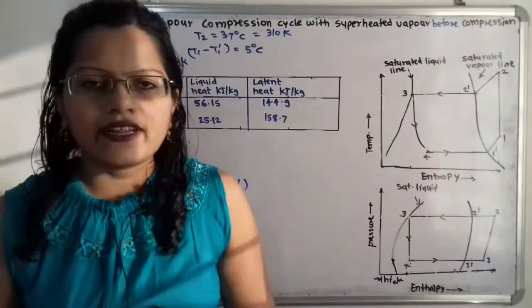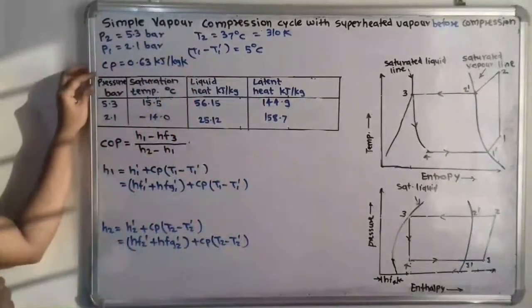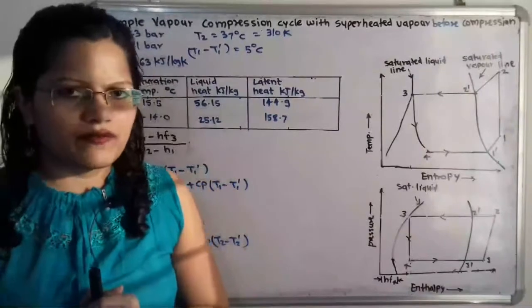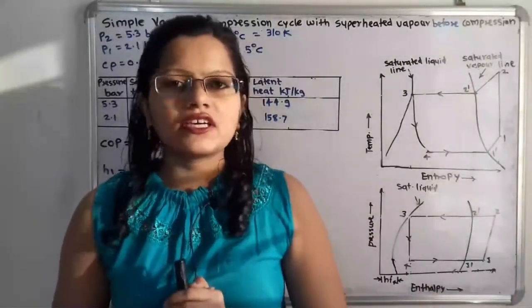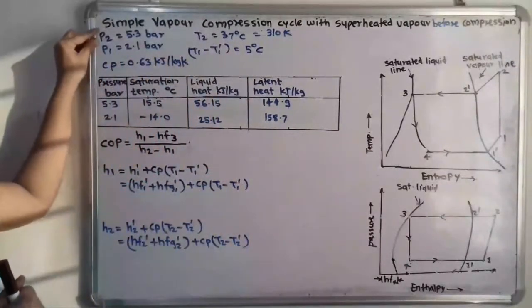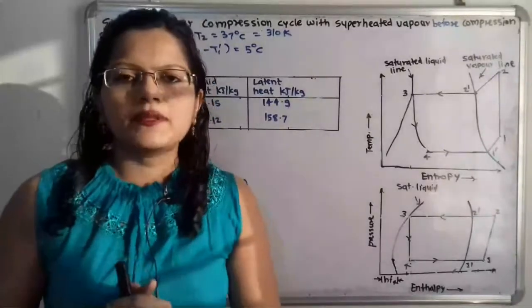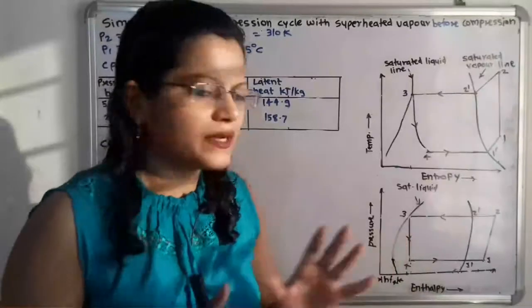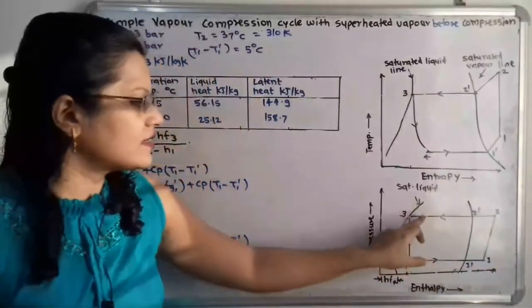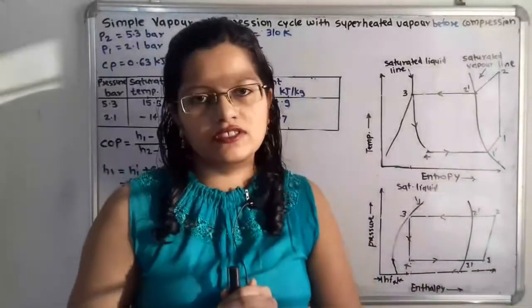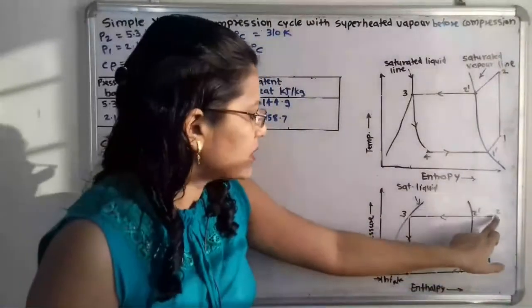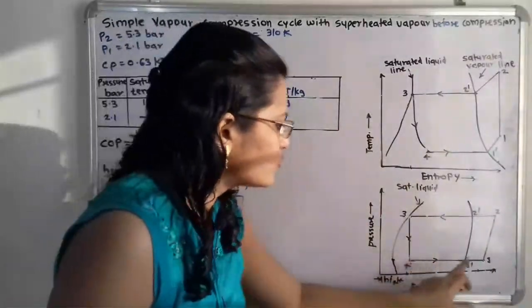We need to find the coefficient of performance of the plant using the data given in the table. The table provides pressure in bar, saturation temperature, liquid heat, and latent heat. Now let us understand the given data. Looking at the pressure-enthalpy diagram, processes 4 to 1 and 2 to 3 take place at constant pressure. Process 2 to 3 is at higher pressure and process 4 to 1 is at lower pressure.